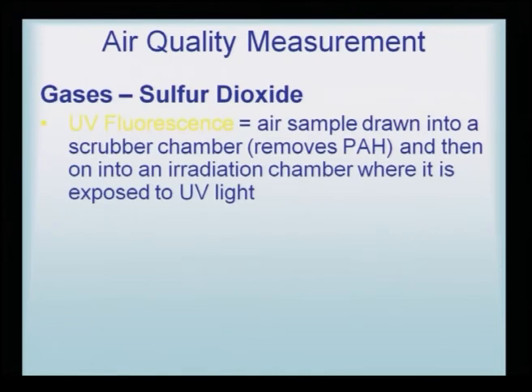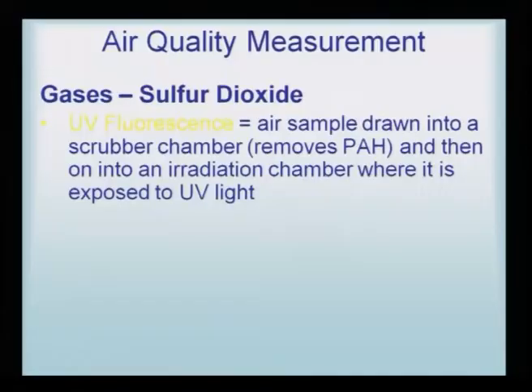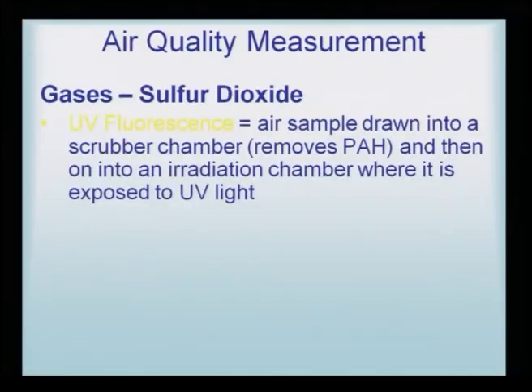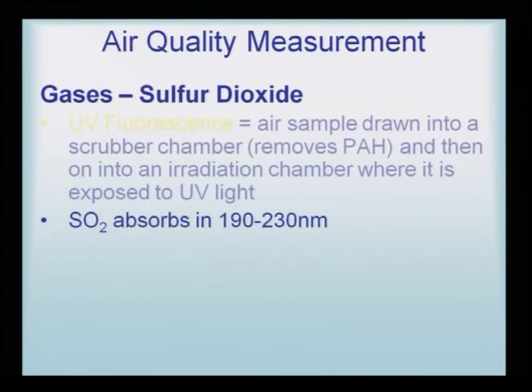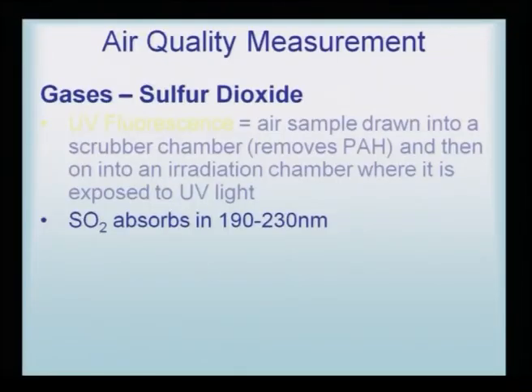Now, there are various methods, and I will give a little bit of detail for the UV fluorescence. Air sample is drawn into a scrubber chamber after the removal of polyaromatic hydrocarbons and then on into an irradiation chamber where it is exposed to UV light. There, the sulphur dioxide gets excited and is analyzed. Sulphur dioxide particularly has a UV absorption between 190 to 230 nanometers, and the UV fluorescence machine actually ranges from 190. So, it is well suited for the analysis.